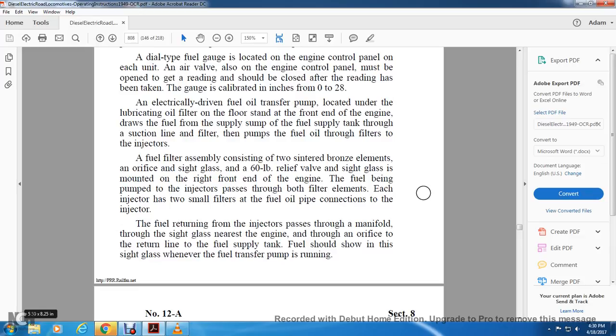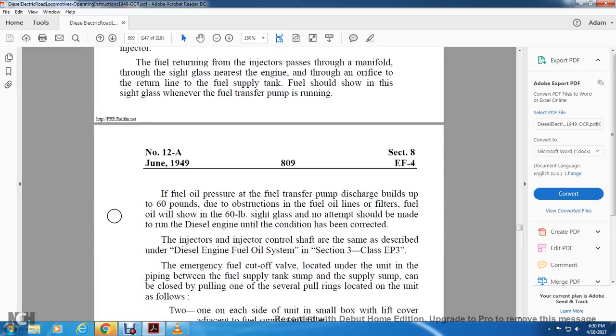Fuel should show in this sight glass whenever the fuel transfer pump is running. If the fuel oil pressure at the fuel transfer pump discharge builds up to 60 pounds because the fuel oil line filters are obstructed, fuel oil will show in the 60-pound sight glass. No attempt shall be made to run the diesel engine until the condition has been corrected. The injector is the same as described in the diesel engine fuel oil system, section 3, class EP3.